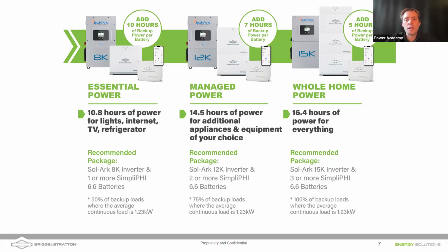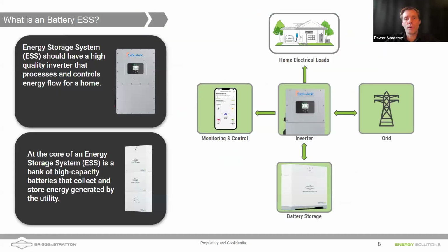And with the 12K, you can hit maybe 75% of the loads in the house, but you're still going to be limited on overall power. And one of the limitations on both the 8K and the 12K is 62.5 amps of pass-through power. So it's really hard to back up a whole home, at least a grid-tied home, with these systems. One nice thing about the 12K and the 15K is you can parallel them. So if you need more overall power, you're able to parallel up to 12 of those inverters.